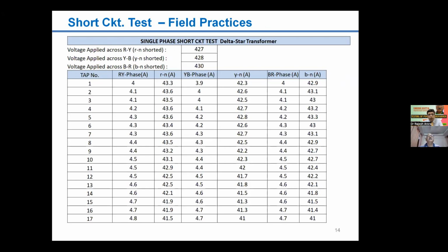These are the results of a healthy transformer. If you look into it, you see that voltage is applied on the HV winding RY with RN shorted, then YB with YN shorted, BR with BN shorted, one by one, and the measurement is done accordingly on all the phases, LV and HV side. Currents are recorded, which you may see here.